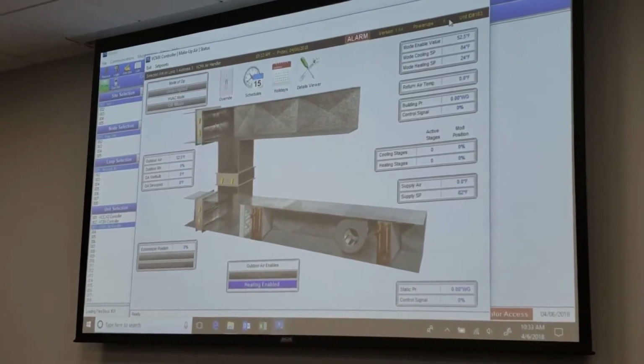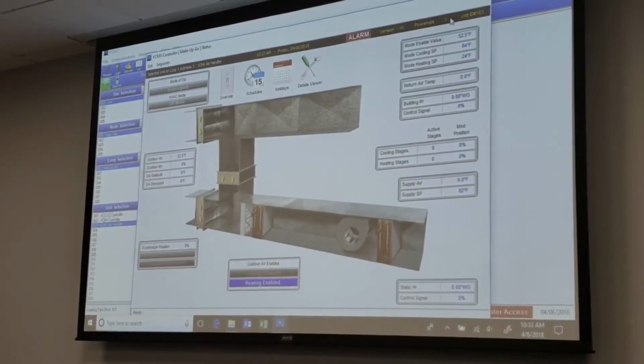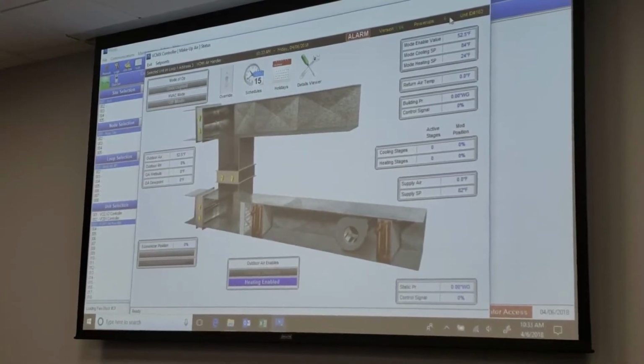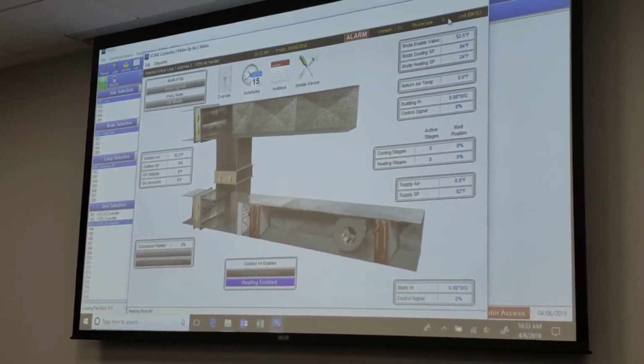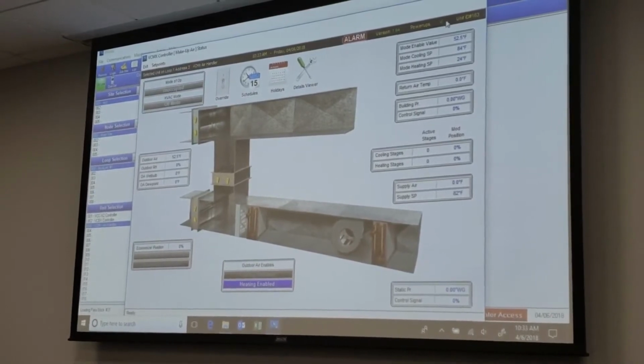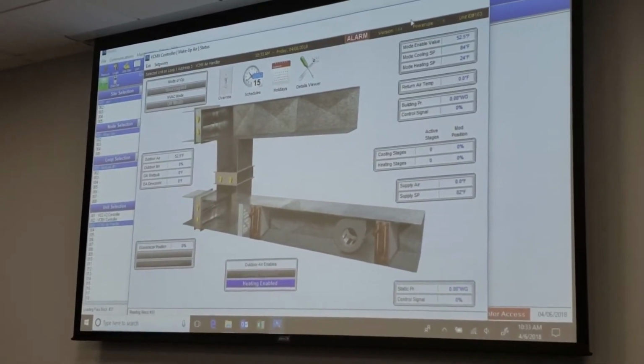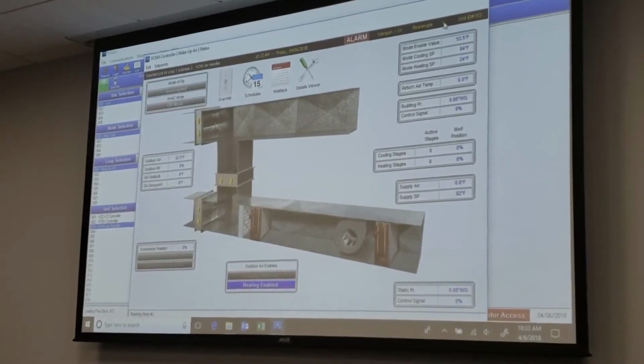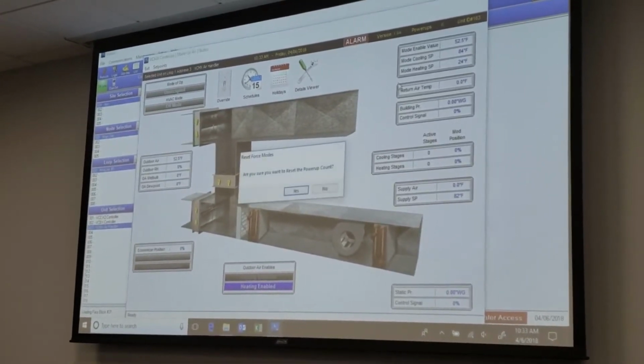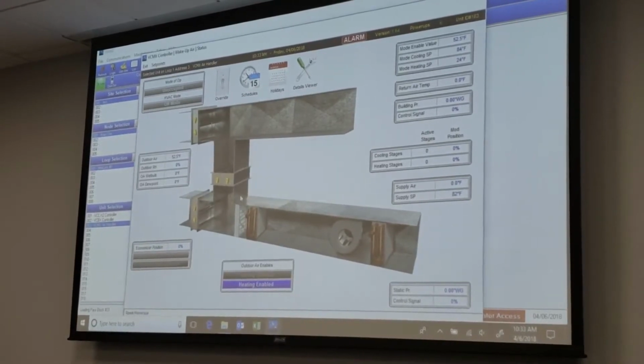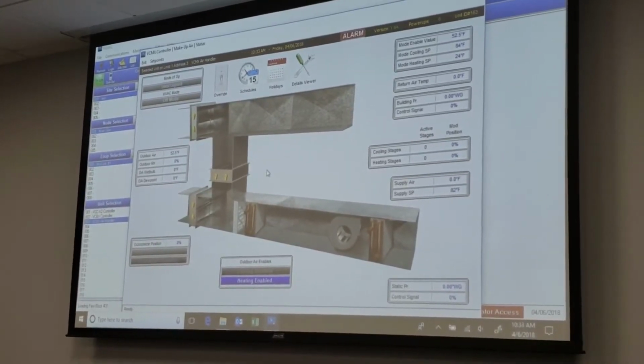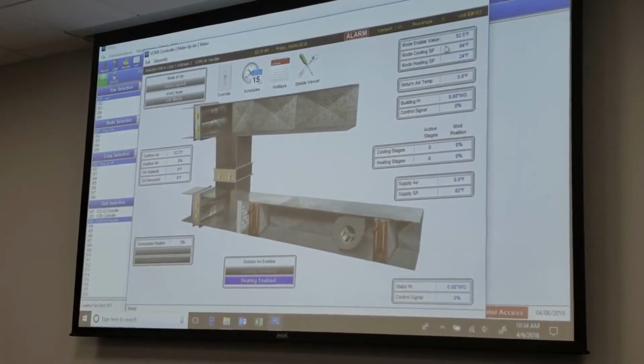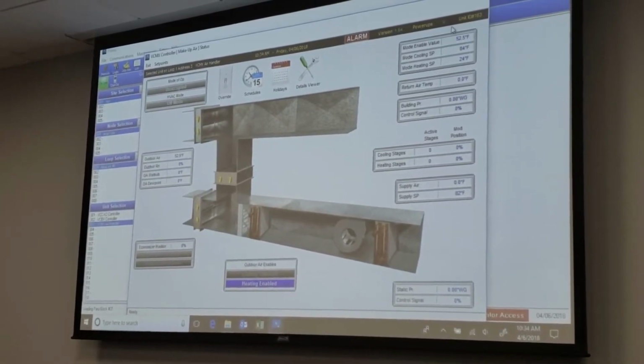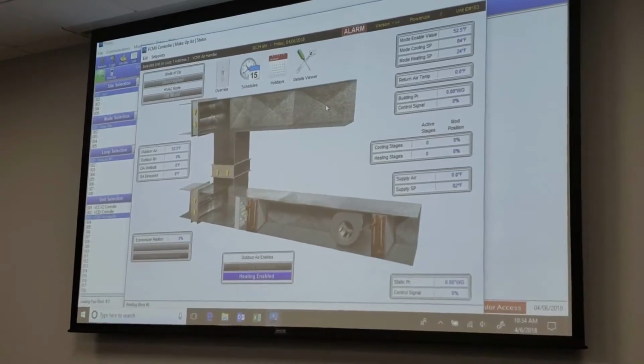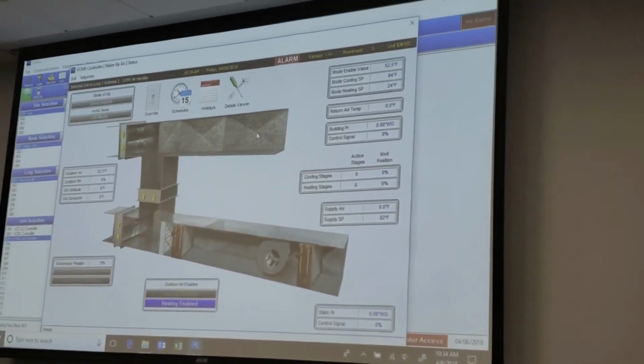We're losing power to this board 1,000 something times. And they said, no, it's not. And it turns out they had something going on in their switchgear. They were losing high voltage power coming to my unit, which was shutting the unit down. And I was able to catch that with power up counts. This one, you can click on it and it'll reset. Reset power up counts, yes. So once I'm done doing maintenance and everything, I can go in there and reset that, and it takes a little while, it went to 0. Then I can start looking to see if somebody's coming in here powering it up, powering it down, see if something's going on there, something electrical.